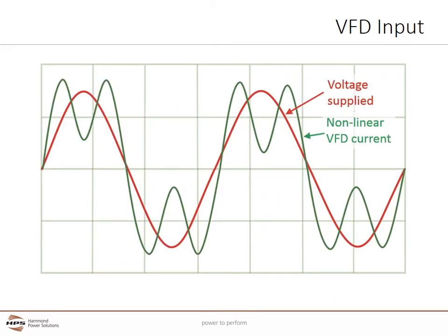The input or line side of a VFD uses rectifiers and is basically a DC power supply. This creates current harmonics when it transforms AC to DC power. As a result, the harmonics distort what's represented here as the utility's perfect red sine wave to look like the distorted green wave. The VFD's input section also has sensors to monitor the incoming power and resultant DC bus voltage. Current harmonics can cause significant issues within a facility, and if they exceed IEEE 519, the utility can fine the user.